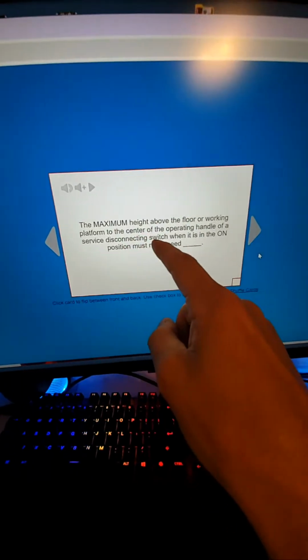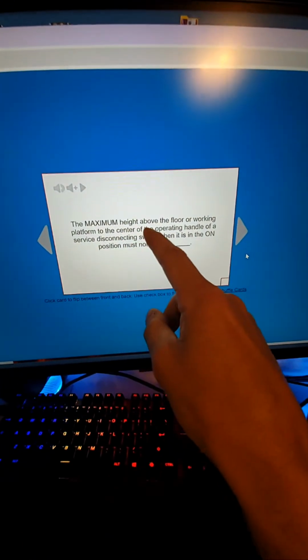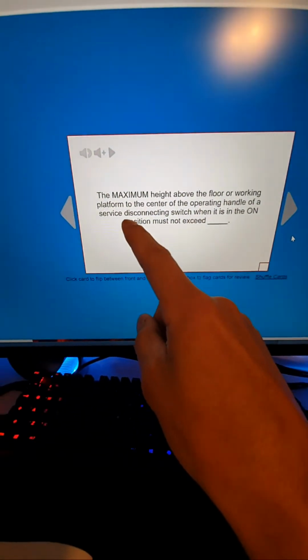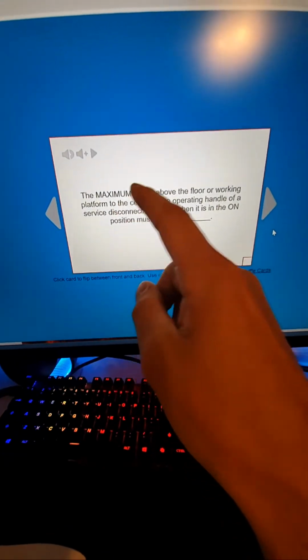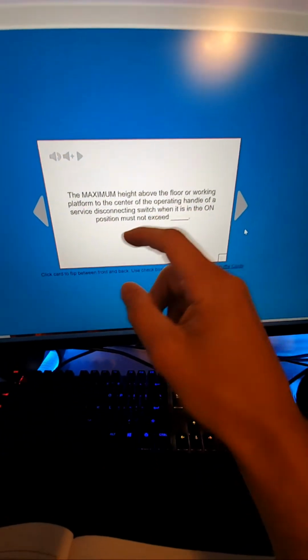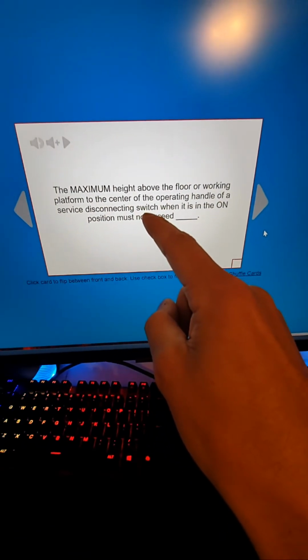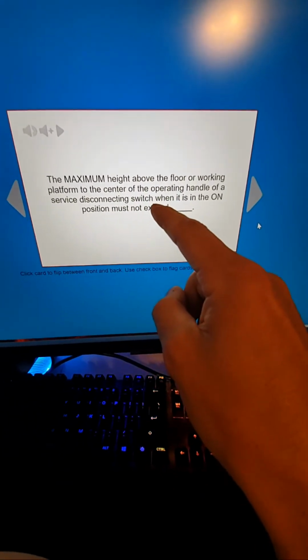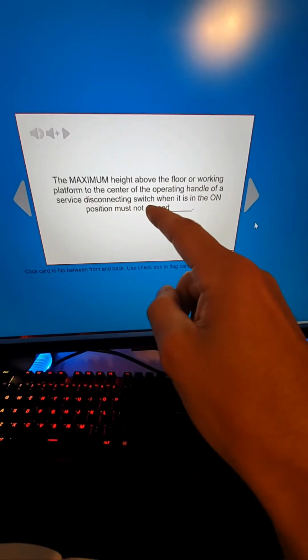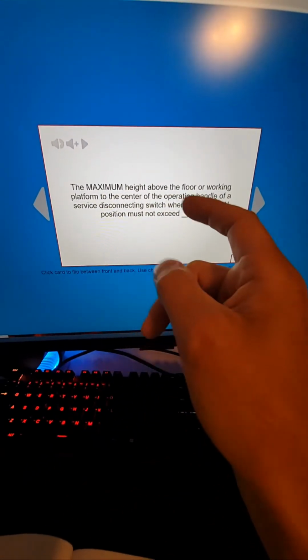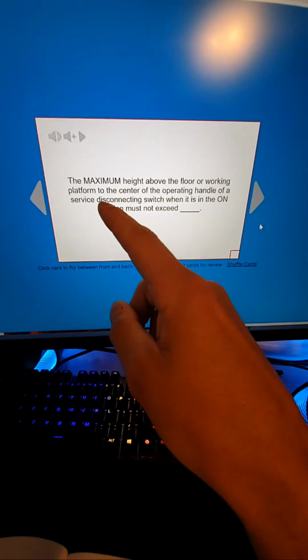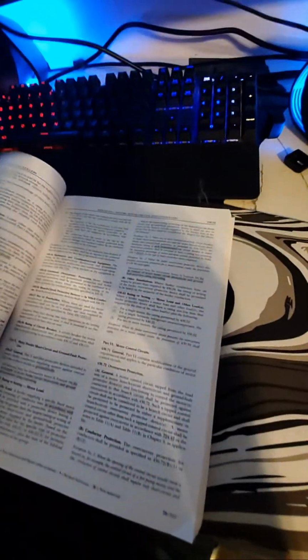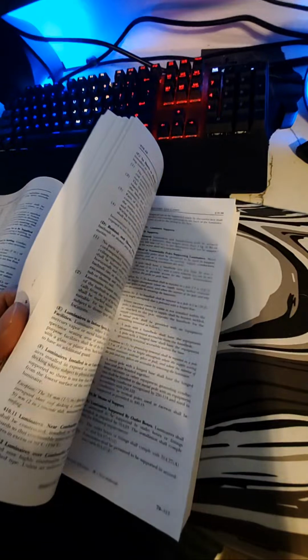We're going to see here, we're going to say switches, right? So this one's kind of tricky. You might want to go into 240 for overcurrent protection, or you might want to go to 230 because it's talking about a service. You might want to go to 240 because it's talking about panelboards, or we can go to 404, which would be switches. So in general, you want to go to the most basic one first and then work your way backwards, because I know 230 doesn't really have a certain height for the services. 240 would be where you might look, or 408 could be panelboards. I think it's 408. Yeah, 408 is switchboards and panelboards.